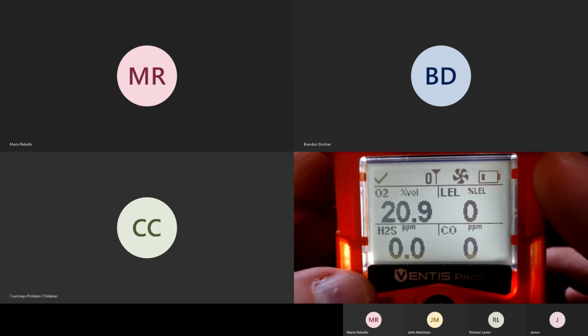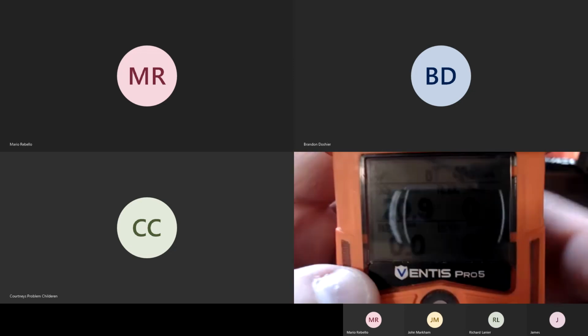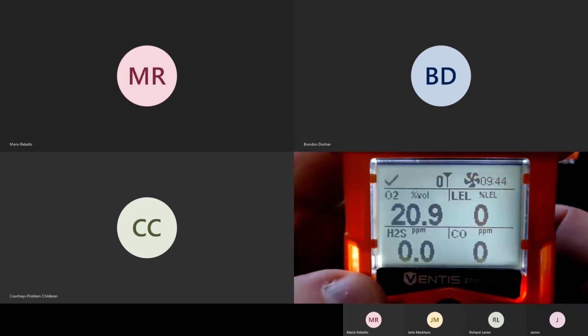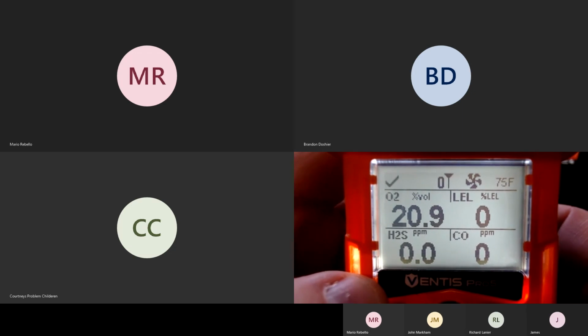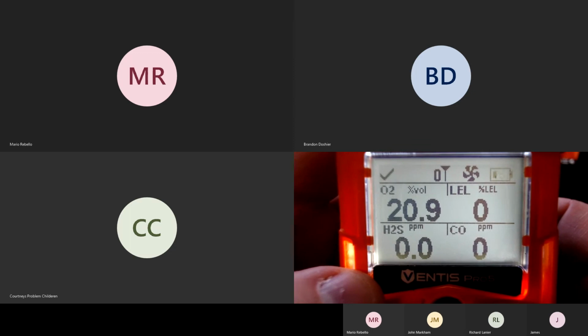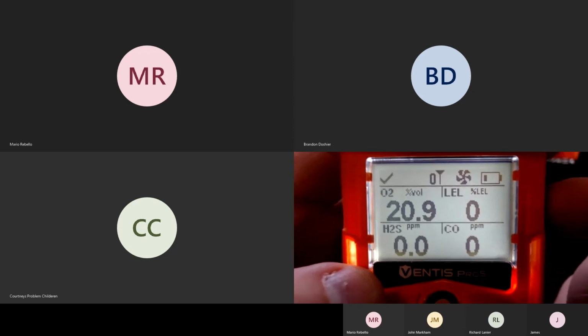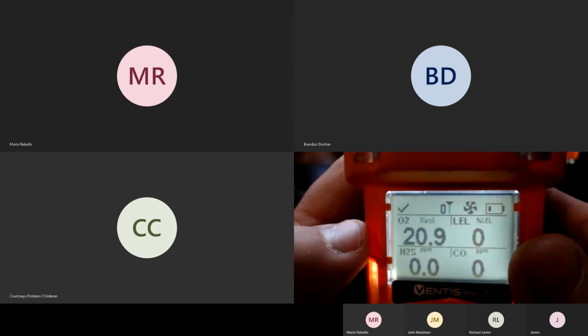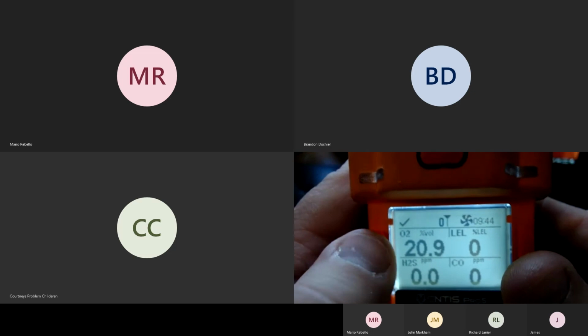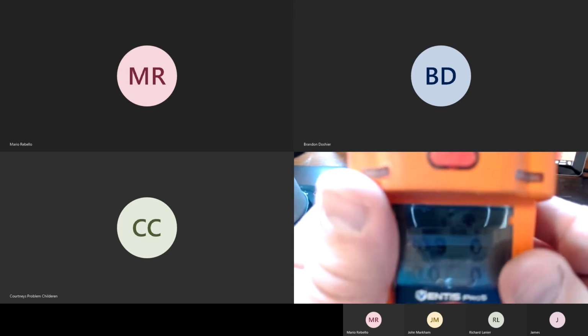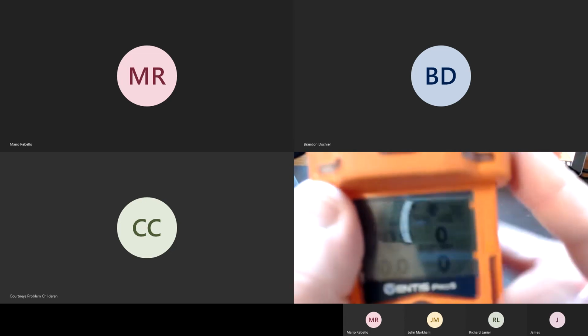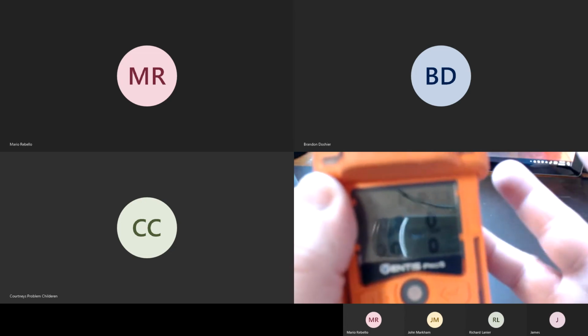In the top right-hand corner, you'll see it's flashing between battery, time, and temperature. Okay, so the time is the current time. The battery is my battery life. And then also the temperature is internal temperature of the instrument. It's not ambient air temperature. Okay, so remember that. That's there so that whenever we have people that are doing readings in extremely cold and extremely hot environments, they know, hey, it's still within its measuring range for that.